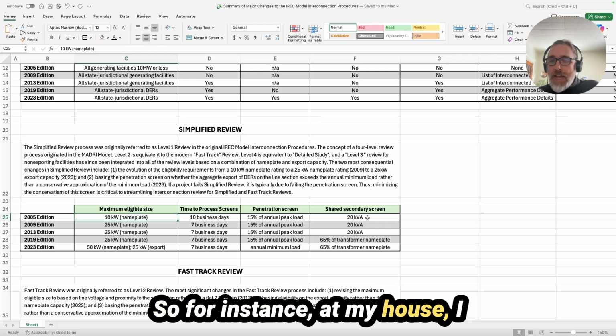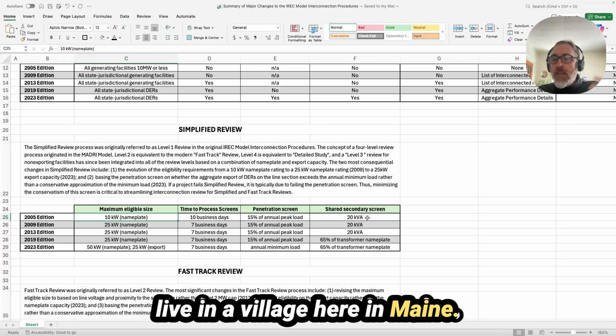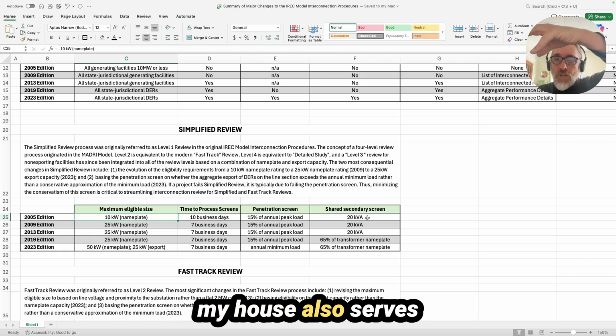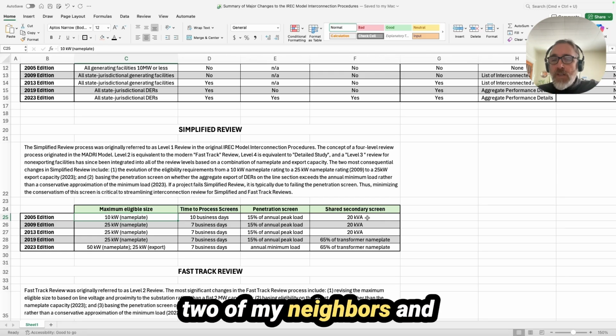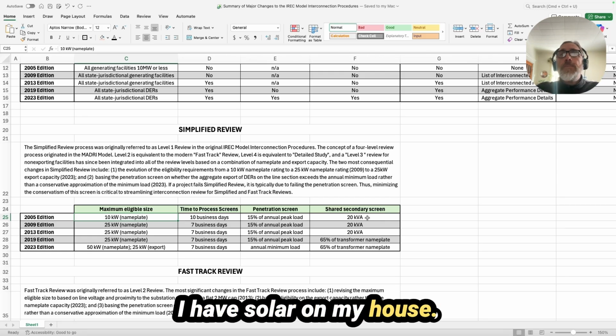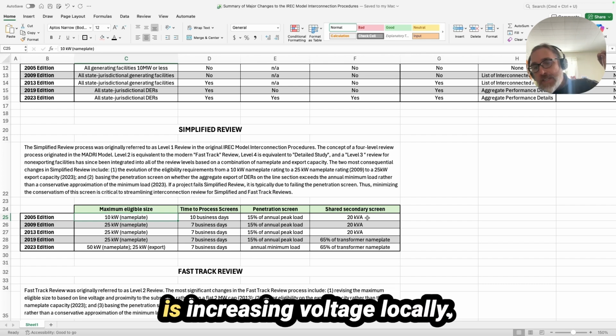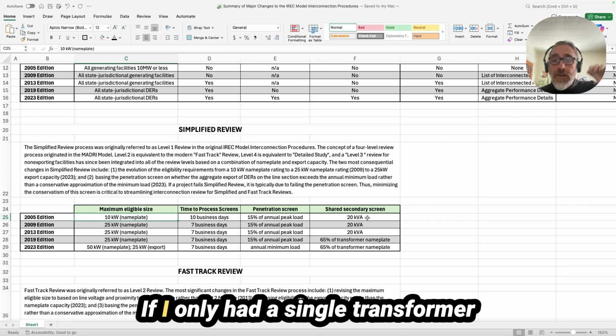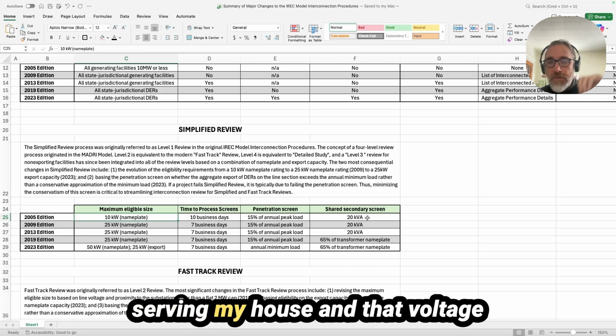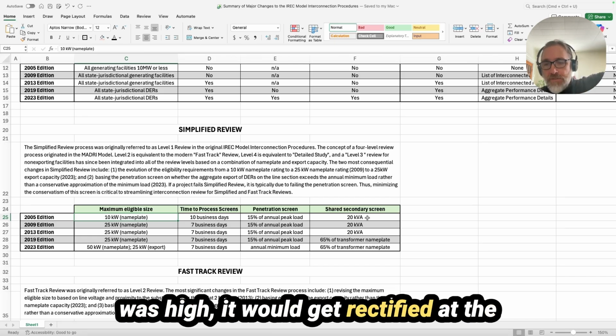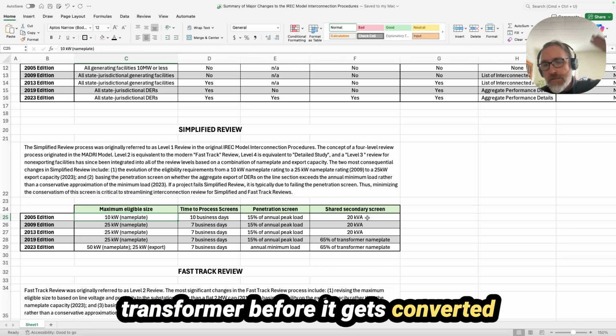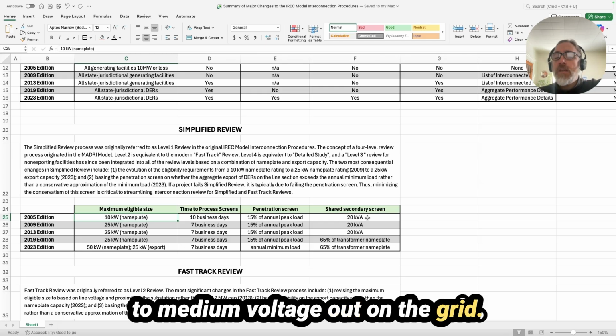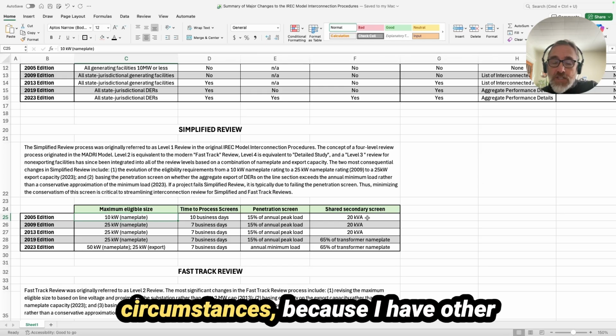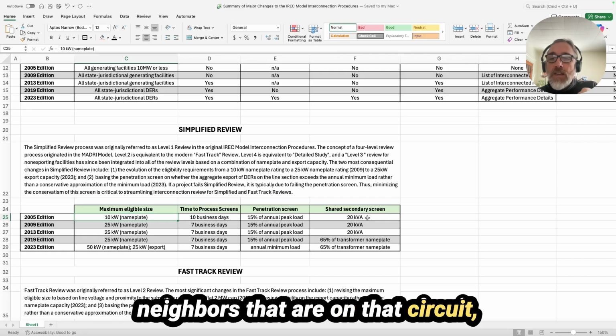So for instance, at my house, I live in a village here in Maine. The transformer that serves my house also serves 2 of my neighbors. And I have solar on my house. The export from my inverter is increasing voltage locally. If I only had a single transformer serving my house and that voltage was high, it would get rectified at the transformer before it gets converted to medium voltage out on the grid.